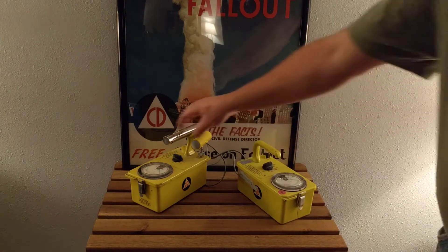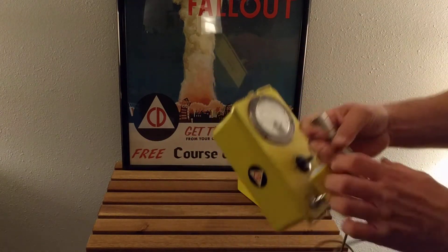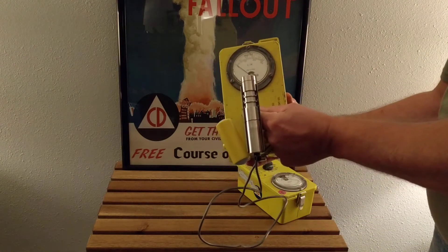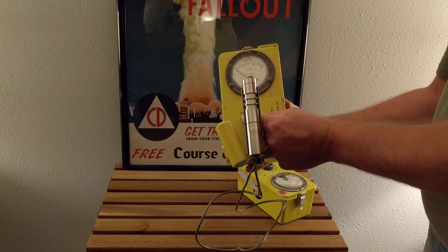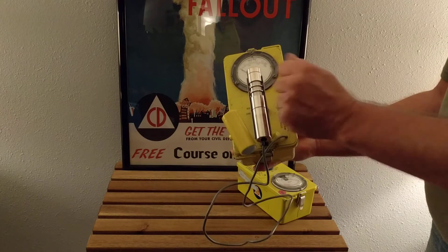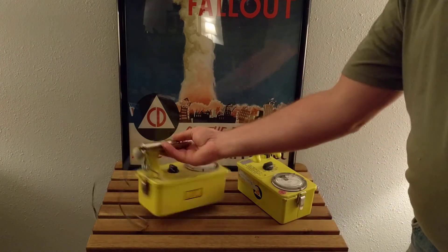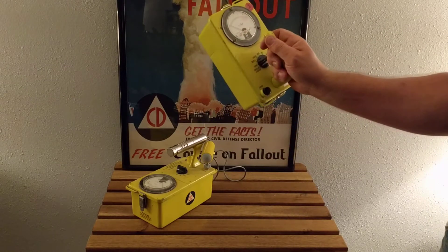This one however reads in millirentgen per hour. At the top end of this, at the times-100 scale — I don't have batteries in it right now — but at the maximum reading it is one blip of the CDV-715 at its lowest reading.